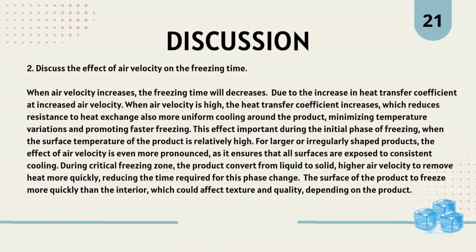For question 2, discuss the effect of air velocity on the freezing time. When air velocity increases, the freezing time decreases due to the increase in heat transfer coefficient. When air velocity is high, the heat transfer coefficient increases, which reduces resistance to heat exchange, and also gives more uniform cooling around the product, minimizing temperature variations and promoting faster freezing. This is important during the initial phase of freezing when the surface temperature of the product is relatively high. For larger or irregularly shaped products, the effect of air velocity is even more pronounced as it ensures that all surfaces are exposed to consistent cooling.